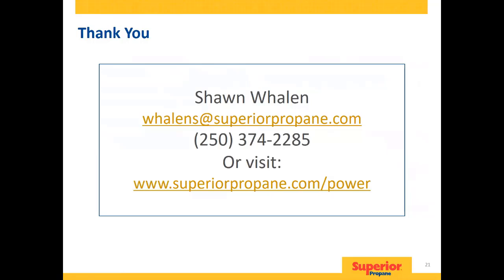Yes, so what I'll do with that is I'll answer it a little bit, and then I'll ask Patrick to weigh in a little bit more, Patrick from Total Power. So, Lake, the power generation system in that application would be a combined heat and power system. Depending on the size of the genset and the load required on the genset, the CHP could take in either heat from the exhaust through a thermal heat exchanger, it could take the free energy from the coolant on the engine, and on a very large unit, you could even use the extracted heat from the engine oil.